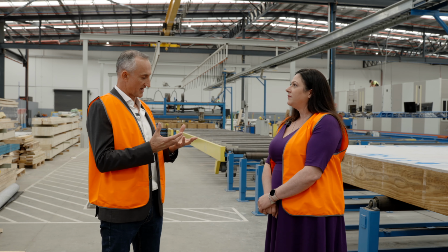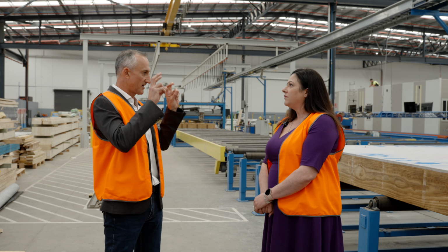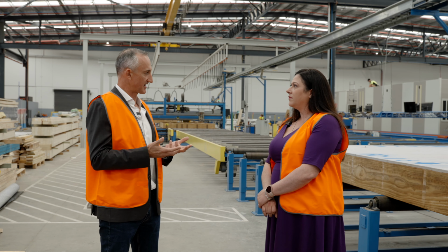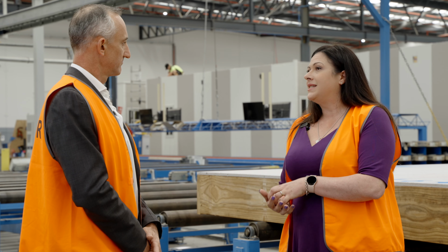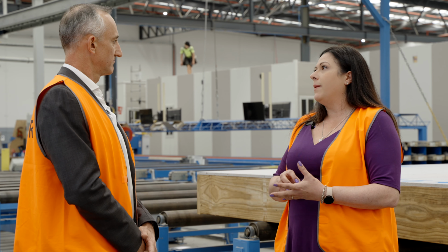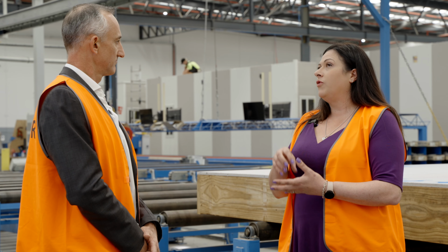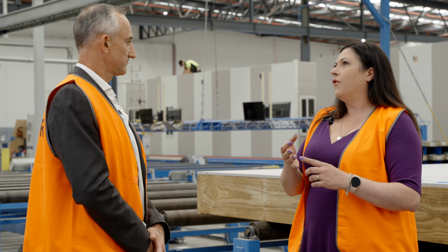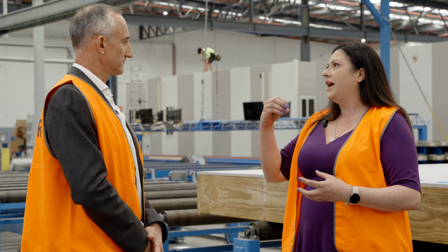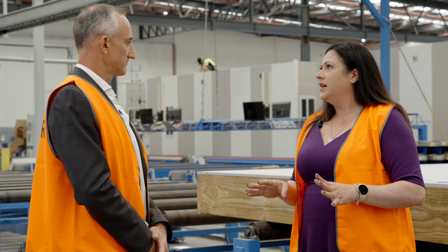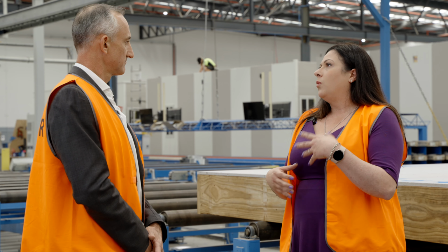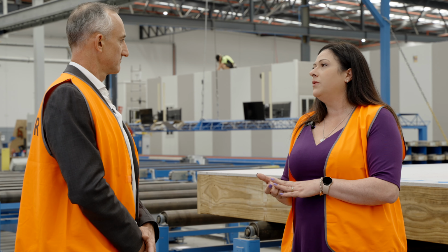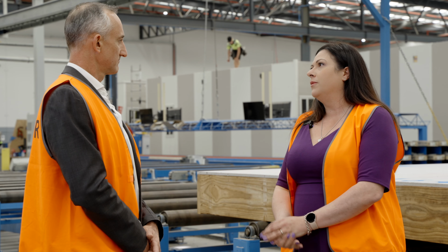The heat recovery ventilator is required because we've created this airtight space within the dwelling. We need to provide a heat recovery ventilation system. What the heat recovery ventilation unit does is like our lungs. It takes out the bad air from the building and replaces it with fresh filtered air from the external. So we're taking air from the kitchens and the bathrooms, extracting all that air and replacing it through the living areas and the bedrooms with fresh filtered air, which also means that there's less pollens, less pollutants, less dust in the building, which means a healthier, cleaner environment for the occupants.